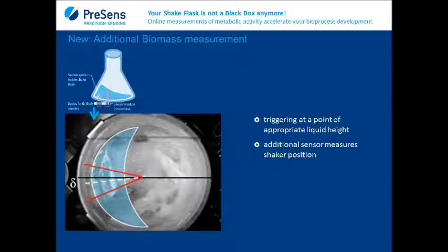How does the biomass measurement work? It's an optical density measurement, so it's actually a light scattering measurement at 560 nanometers. And if you imagine a running shaker, of course the fluid height in the shake flask varies all the time. And if you want to have an accurate biomass measurement, you need to make sure that the fluid height is always the same at the moment you do the measurement. So in the Shake Flask Reader Vario, there is an integrated G-force sensor that makes sure that the biomass measurement is always triggered at the same fluid height. So if you change the shaking speed during the measurement, the G-force sensor will automatically recognize that and trigger the biomass measurement at the same fluid height, as at a different shaking speed.